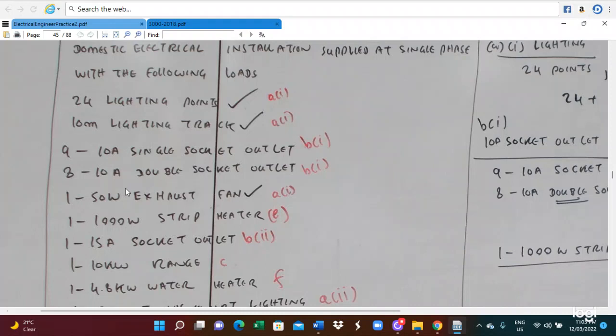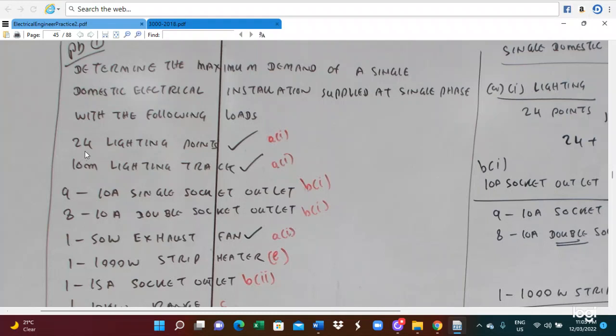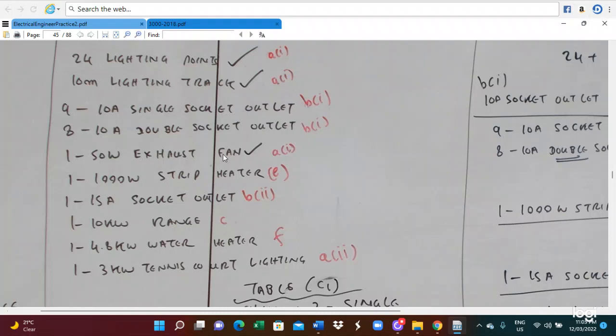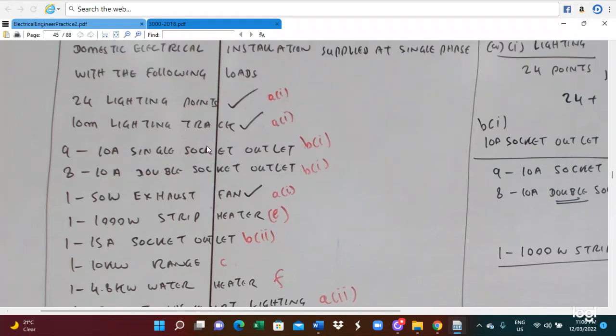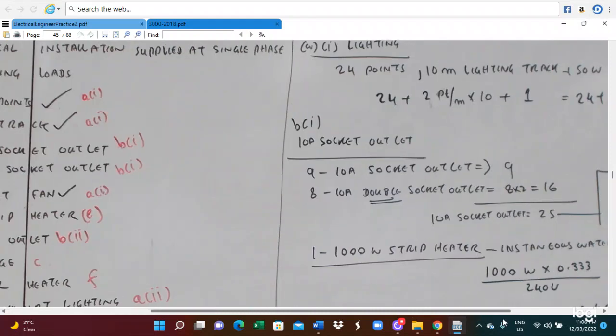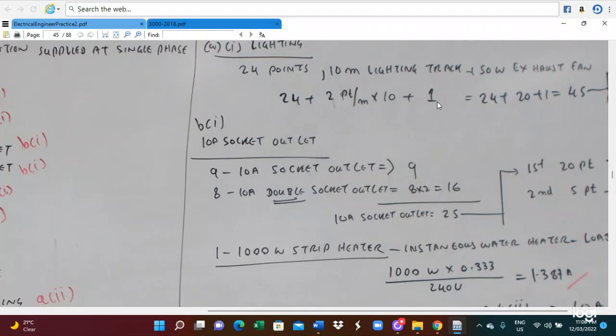So what are the light points now? They are the 24 lighting points, the 10 meter lighting track, and the 50 watt exhaust fan. So there are 3 kinds of light points. One is the 24 lighting points, next is the 10 meter lighting track, where every 1 meter is equivalent to 2 points, so 2 multiplied by 10, and also the 50 watt exhaust fan, which we can regard as a light point. So how many points are there? 24 plus 2 multiplied by 10 plus 1, so there will be 45. So there are 45 points.